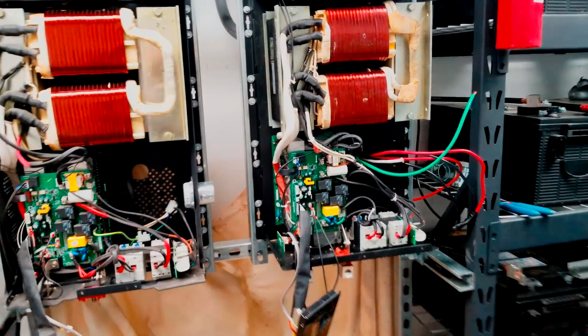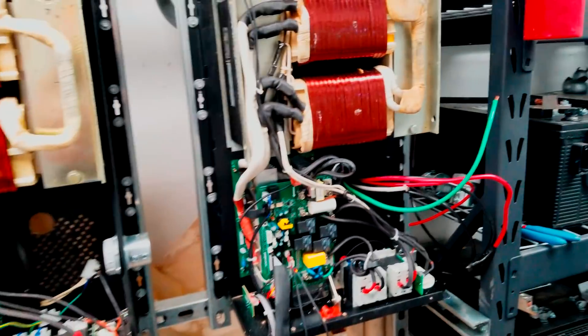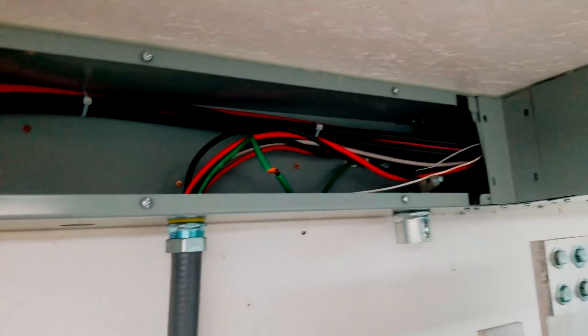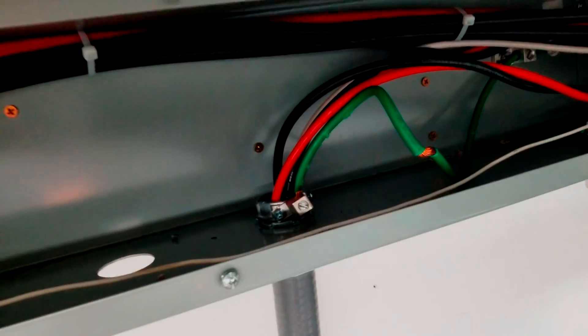So here I began getting the electrical in. I punched a one-inch knockout in the back. I still need to get a bushing on there. That comes out through here through some seal tight up into my gutter. I've got my wires in. I just need to connect on to this grounding bushing up here.